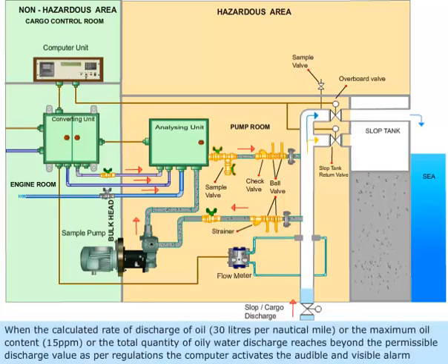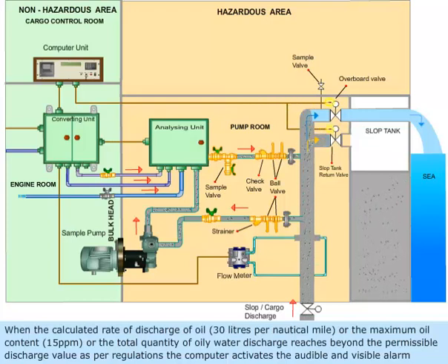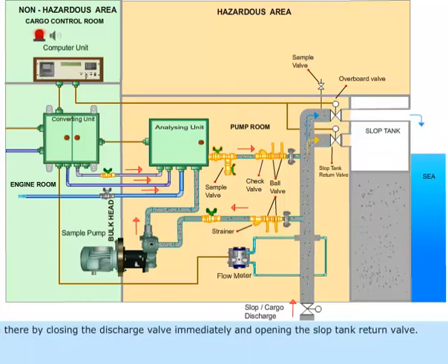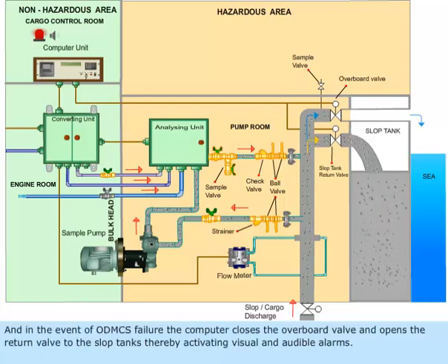When the calculated rate of discharge of oil exceeds 30 liters per nautical mile, or maximum oil content of 15 ppm, or the total quantity of oily water discharge reaches beyond the permissible discharge value as per regulations, the computer activates the audible and visible alarm, thereby closing the discharge valve immediately and opening the slop tank return valve. The cargo or slop pump should then be stopped. In the event of ODMCS failure, the computer closes the overboard valve and opens the return valve to the slop tanks, activating visual and audible alarms.